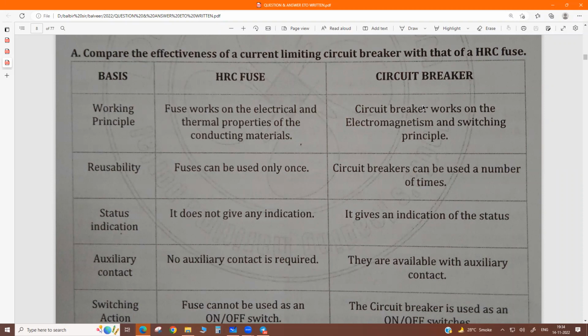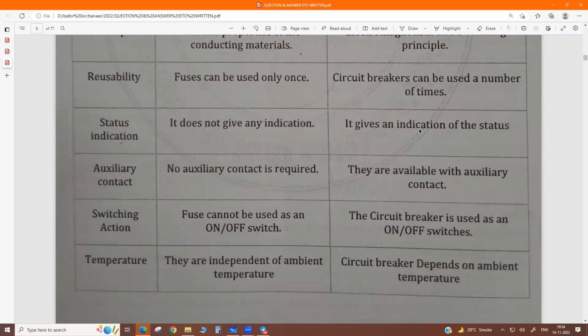Now your breaker works on the electromagnetic principle. On reusability, a fuse is used only one time, but a breaker has 10,000, 20,000 on-off operations. Now in a fuse there are no indications, but in a breaker we know the status with auxiliary contacts. In a breaker there is a main contact and auxiliary contacts. By using auxiliary contacts we can provide on, off and trip indications. And here there is no auxiliary contact. Now in a breaker, the fault current is sensed by the CT and relay, which communicate to the trip coil of the circuit breaker. That's why the fault clearing time, the fault tripping time, is higher in a circuit breaker. In a fuse it is less. Sorry, in the case of an HRC fuse, it is a lower operating time. Okay.